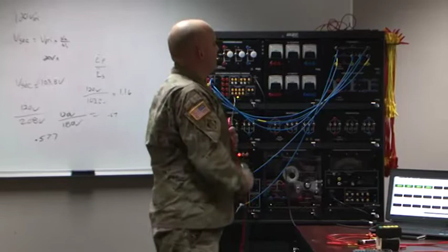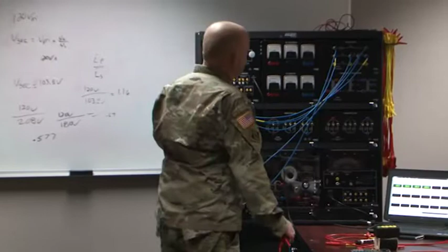But now what I want to do - let me back up and make a note. Based on this ratio here, if I was to apply 120 to this lower set of windings, that's why it's important not to do it, because now this winding reference is going to be way higher than 120 - higher by our scalar here, this 1.16, we're going to jump it up above what that voltage rating is.